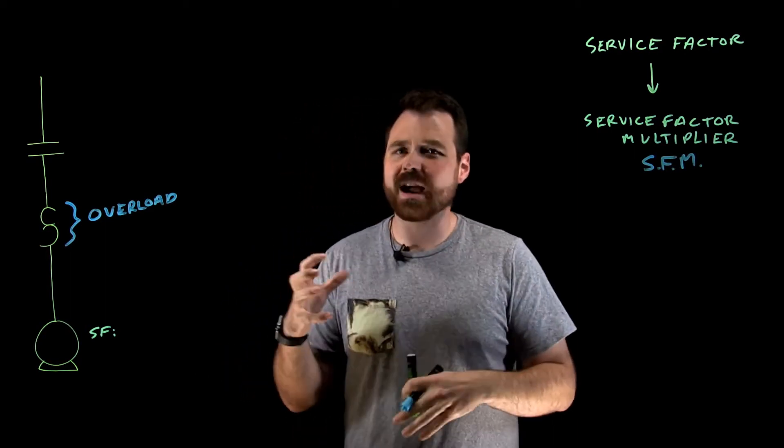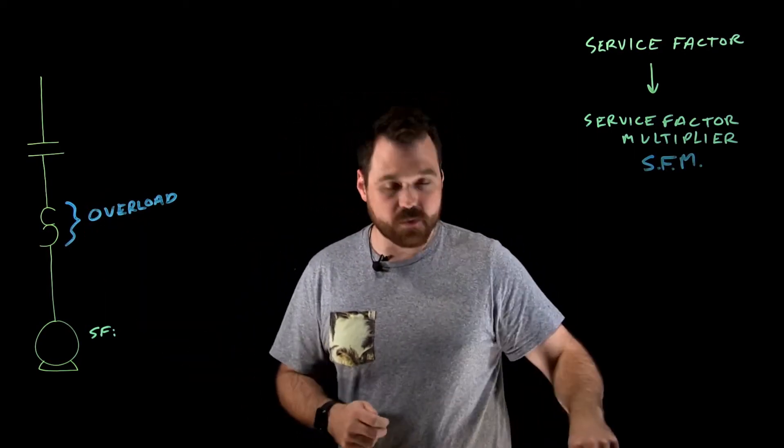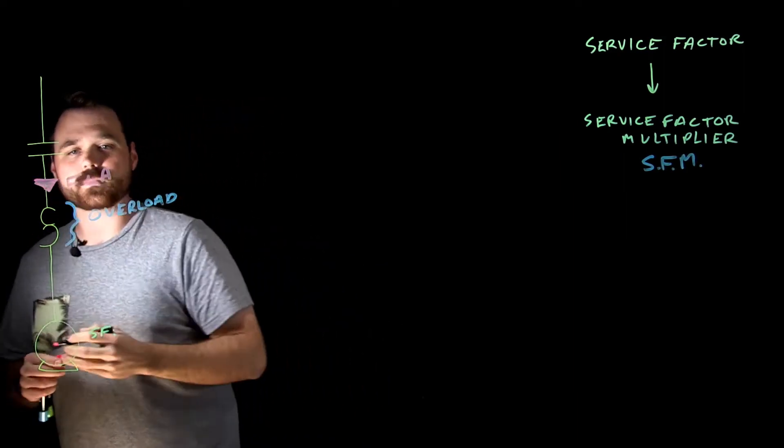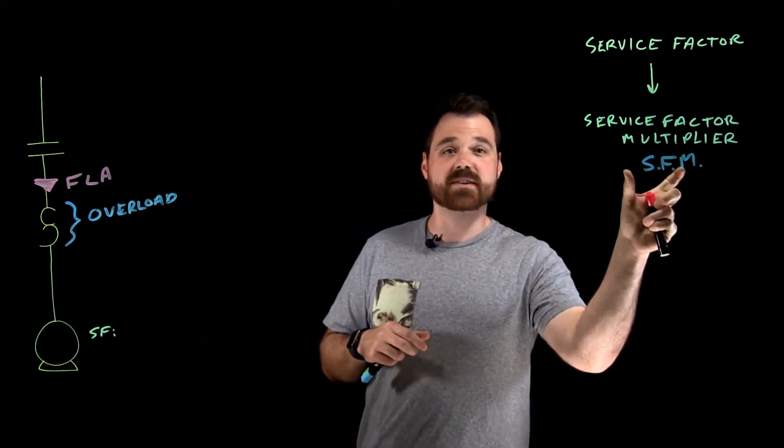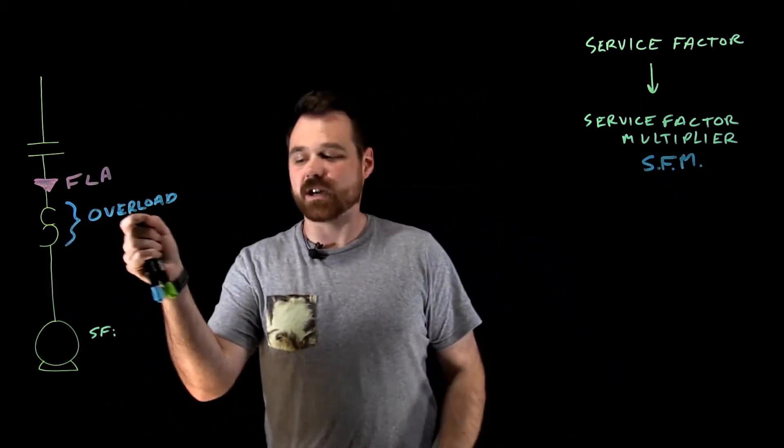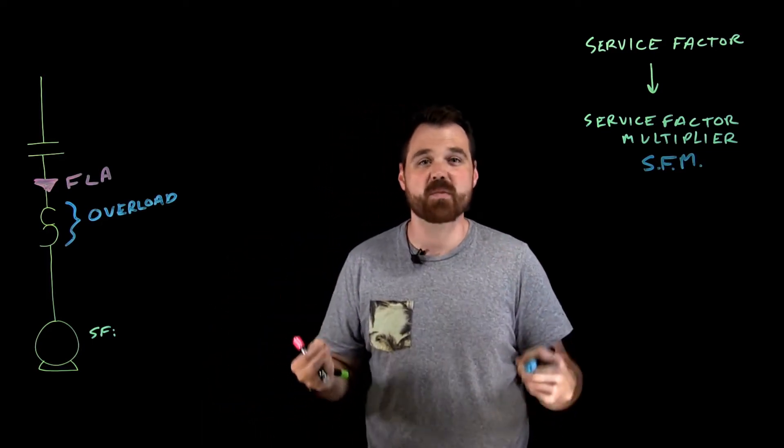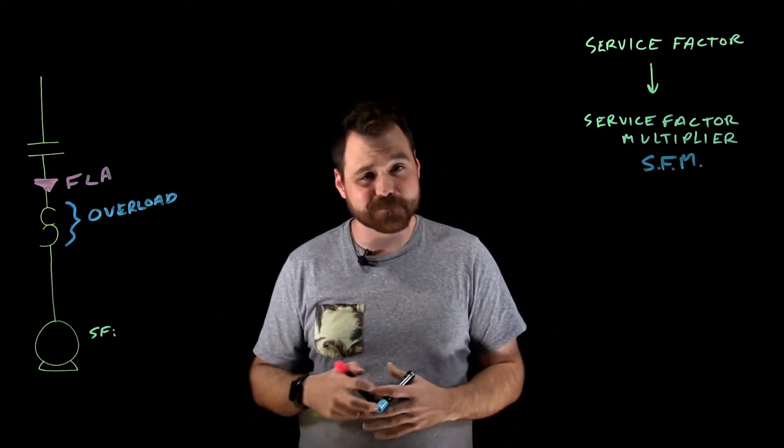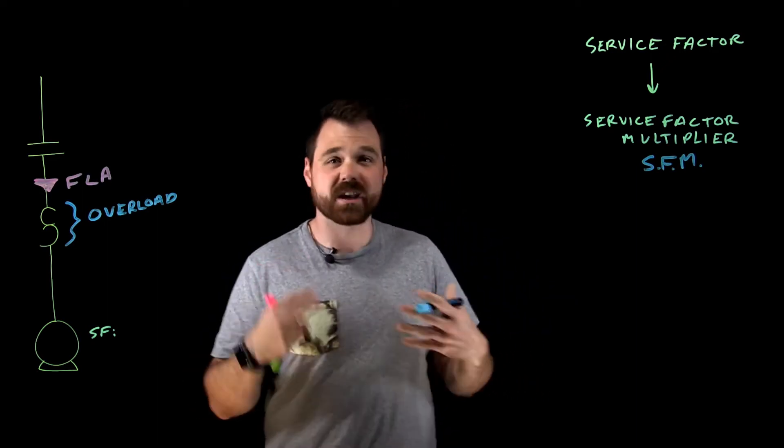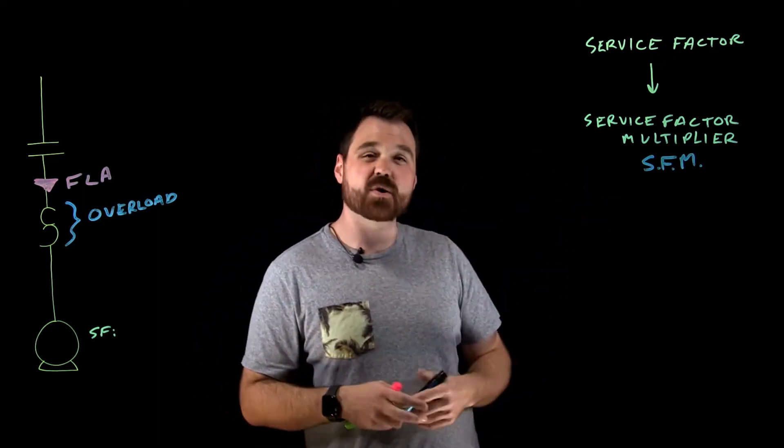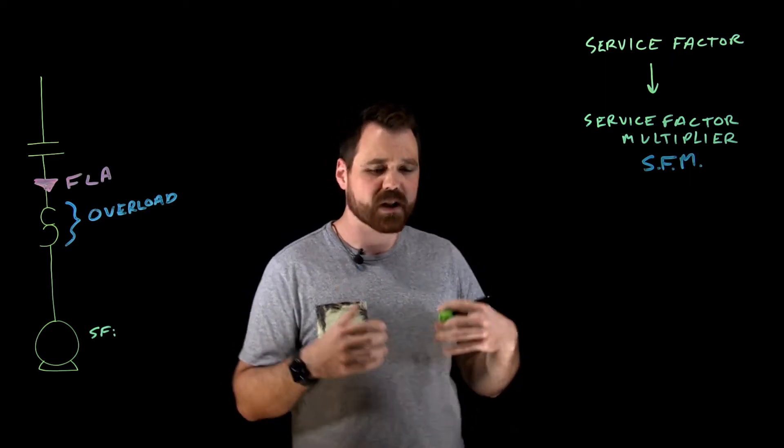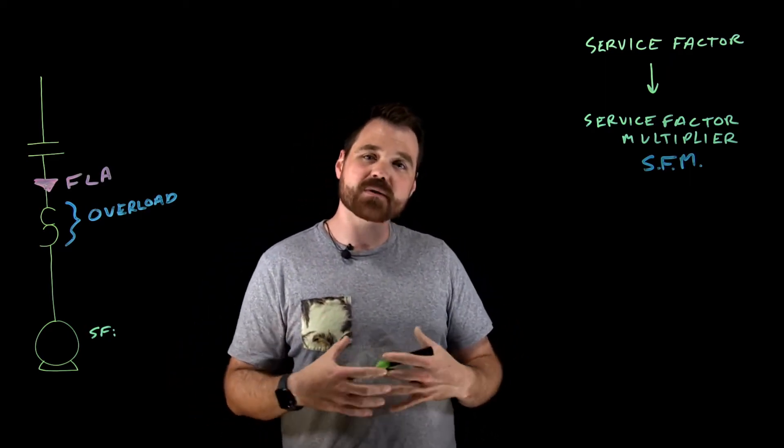The code allows us to take the FLA of the motor. We know that there's going to be a FLA flowing through that motor. We multiply it by the service factor multiplier, and that tells us our overload setting or the maximum allowable overload setting. I'm not going to do any calculations here. I just want to quickly review how that service factor multiplier works.